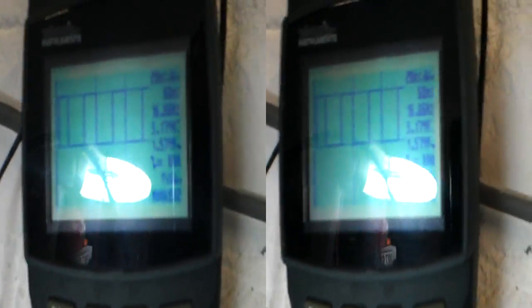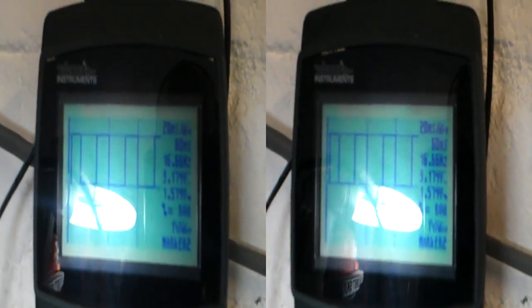So currently it's running at 16.66 Hz, right? Now I actually calculated by just stepping it that it's actually a 4-pole motor, okay?